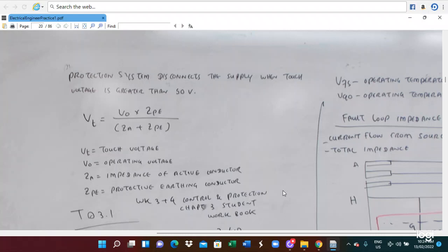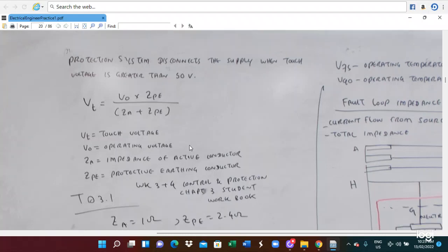Now when we are installing electrical equipment, we have to be aware of the protection system. The protection system simply disconnects the supply when the touch voltage is greater than 50 volts. This means that the allowable touch voltage is 50 volts. So before you disconnect any equipment from the supply, you have to be aware of how much touch voltage can happen. So this is the formula to calculate the touch voltage.